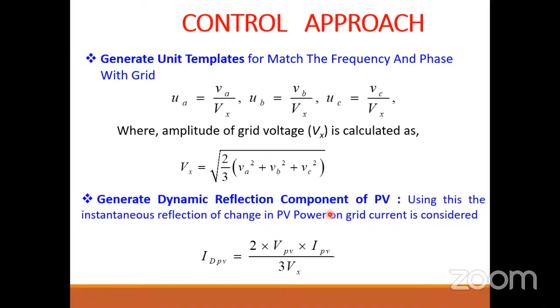We will try to find out all those components for the input terminals, the PV components. So we take the PV power, divide by the magnitude, which is the PCC voltage magnitude, multiply and divide accordingly, and you get the IDPV. This is also known as the dynamic component, or generated dynamic reflection component, sometimes called the PV feed-forward component, or the PV current, the PV AC equivalent current of the PV DC power. Different literature uses different names, but the component is the same.